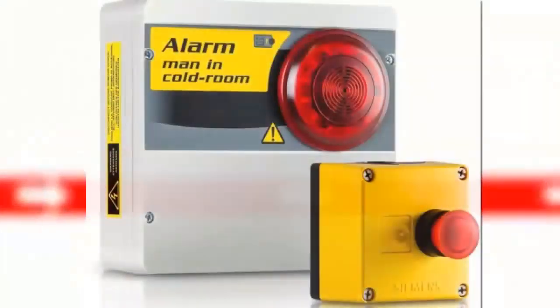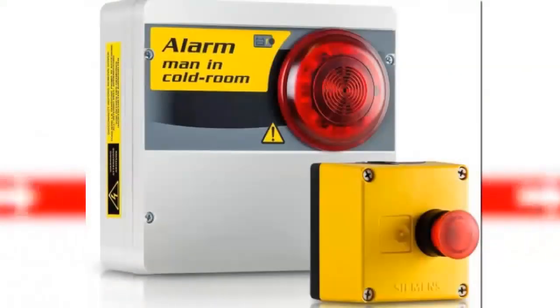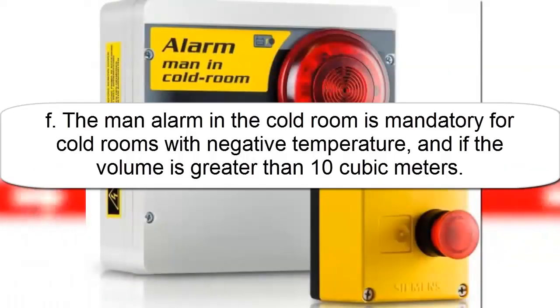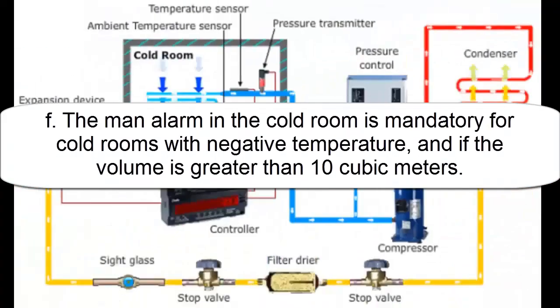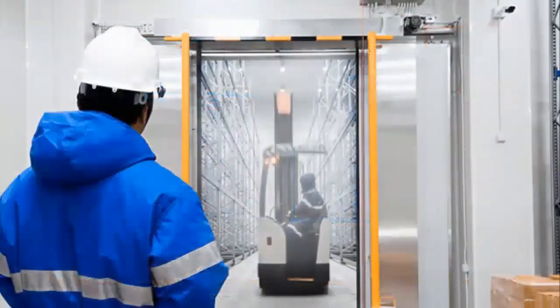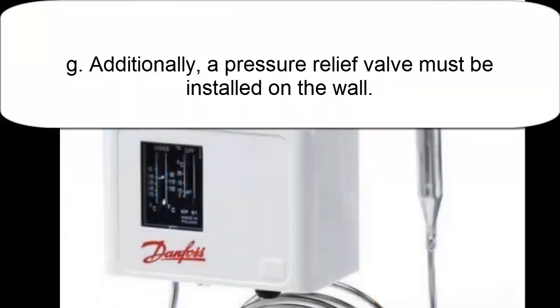F. The man alarm in the cold room is mandatory for negative temperature cold rooms, and if the volume exceeds 10 cubic meters. G. Additionally, there must be a pressure relief valve on the wall to equalize the pressure between the room and the environment with two-way depression.